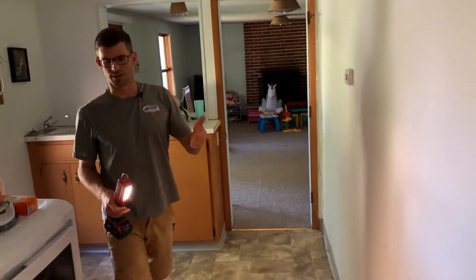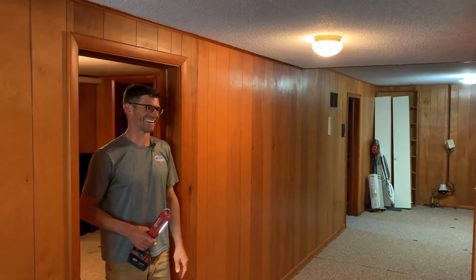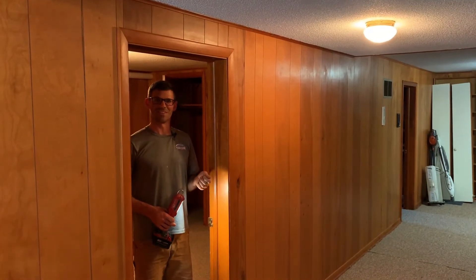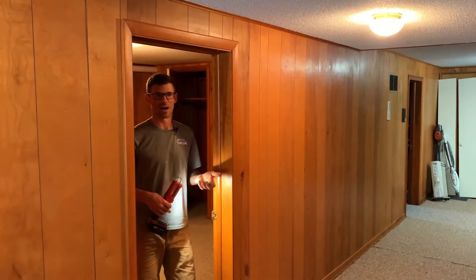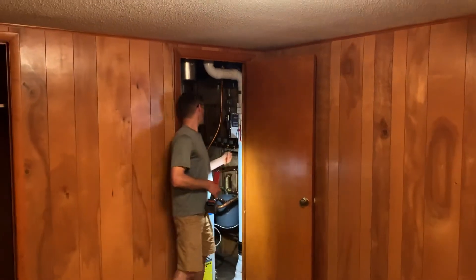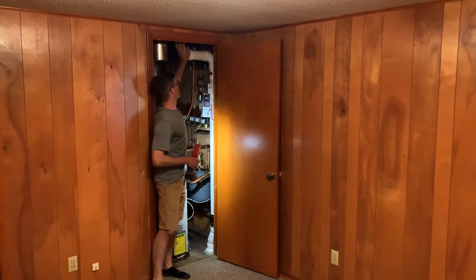There's not much to see upstairs since the pipe runs through the chase and the attic is too hot to revisit. We ended up using a Fantech RN4 EC fan dialed to seven, which gave us the pressure field extension we were looking for. We're running 83 watts and approximately 60 CFM, estimating about 25% of that coming from the house as conditioned air loss. Operating costs are estimated at about $184 per year.